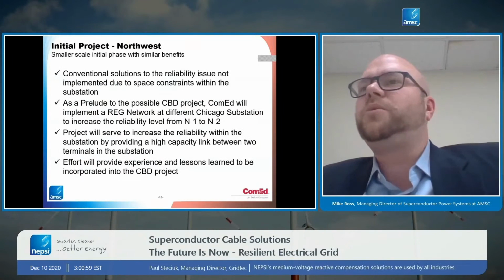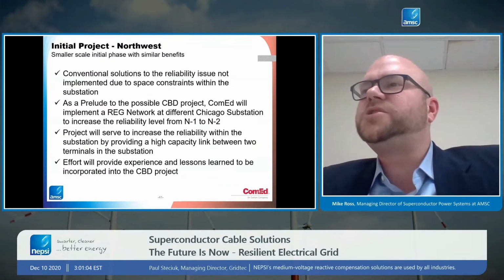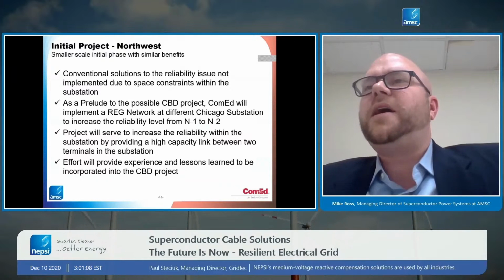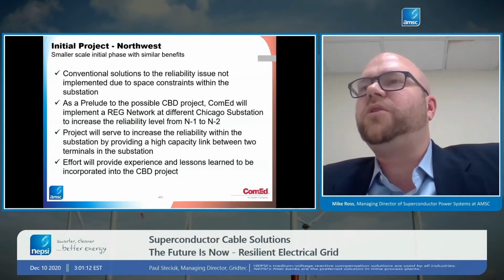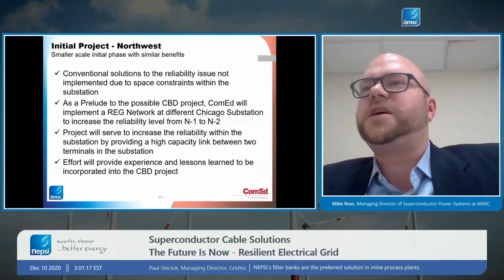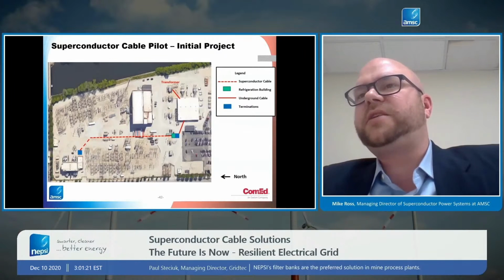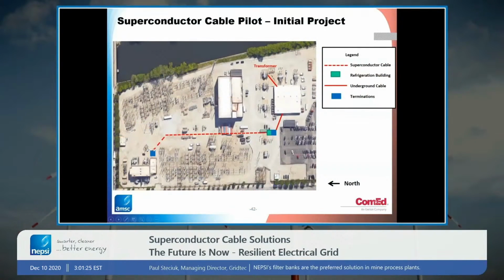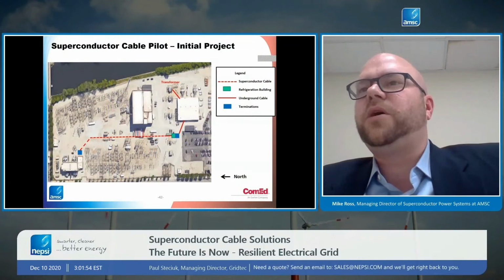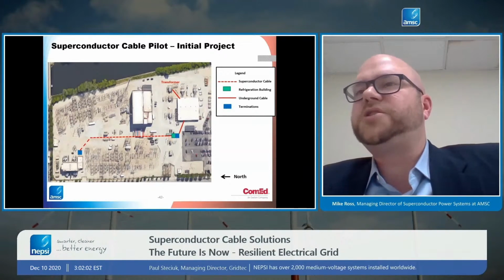Before we get into that big project, we're installing a phase 1 of the project at a substation nearby, where we're showing ComEd how this project will be installed in the downtown area. So we're doing all the things that we would do in the downtown area, but in a smaller project within a substation. So this is an idea of that project. So what we're doing is we're connecting different sides of the substation together with a superconductor cable. Same voltage, same rating, same terminations, same splices as the main project, but at a smaller scale, so that ComEd can demonstrate the technology and get comfortable with it before it gets deployed in their downtown area. So this project is under construction today, and I think we are likely to have a future tech talk with ComEd to talk about more details of this particular project.